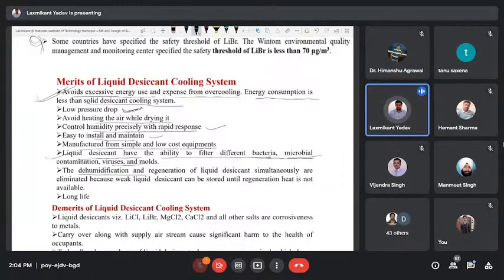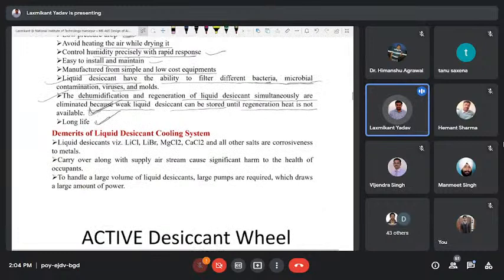The dehumidification and regeneration of liquid desiccant need not occur simultaneously, because weak liquid desiccant can be stored until regeneration heat is available. So this is one of the great features of the liquid desiccant. Another is the long life. What are the demerits of liquid desiccant cooling system? The liquid desiccants, lithium chloride, lithium bromide, and all salts are corrosive to metal. So this is one of the concerns. So during the designing of the duct, carryover along with the supply air stream causes significant harm to the health of the occupants. This was already told.